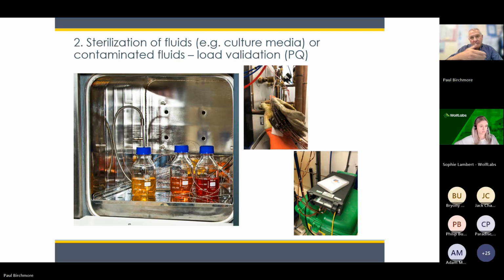And now you can use that data, write a report, show that the variation in temperature is minimal, and you've got your audit trail to prove that you've got a load validation process or a performance qualification, part of your IQ, OQ, PQ process. You'd set that into a written SOP, which basically decides how many bottles of which material and how much liquid, and that's your SOP. You could do it again for a different size bottle, a different number of bottles, a different type of media, and you then rerun the same load validation protocol. And you do each one of the sizes of bottles, each individual type of load, until you've got a whole set of SOPs for all your load validation protocols.